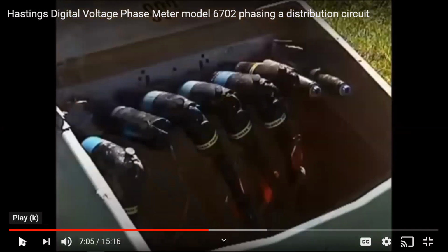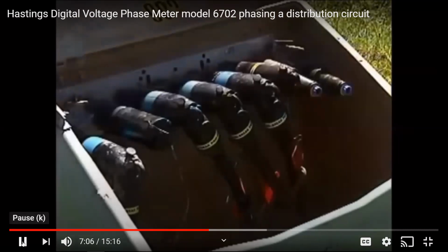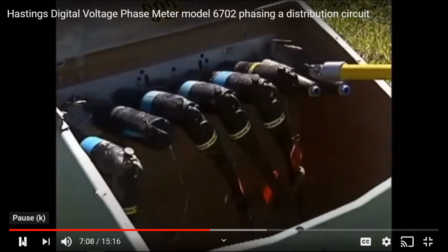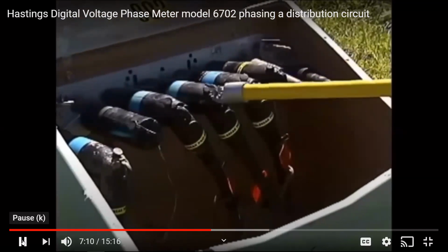Okay, so with the situation, what he's got going on here for the test purposes is he's got one energized primary coming in, and these three cables that he has right here have three different types of fault conditions on them. And we're going to need to take notes on those to find out what kind of fault they have on them. So I just want to give you a heads up on that. This is an 8300 volt underground system that we have, 4800 volts line to ground.